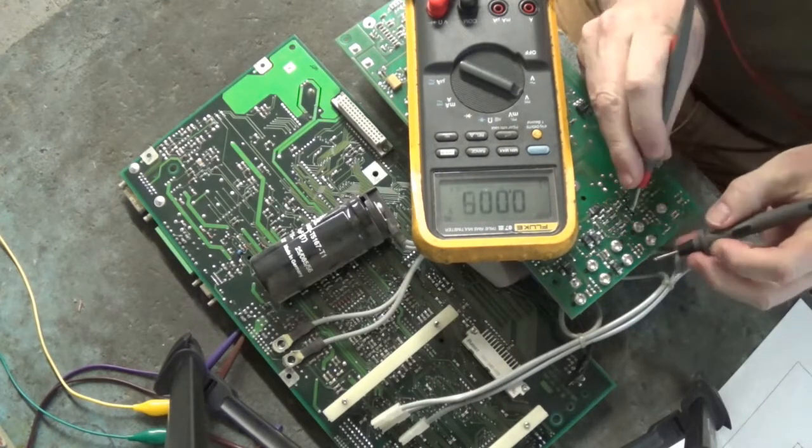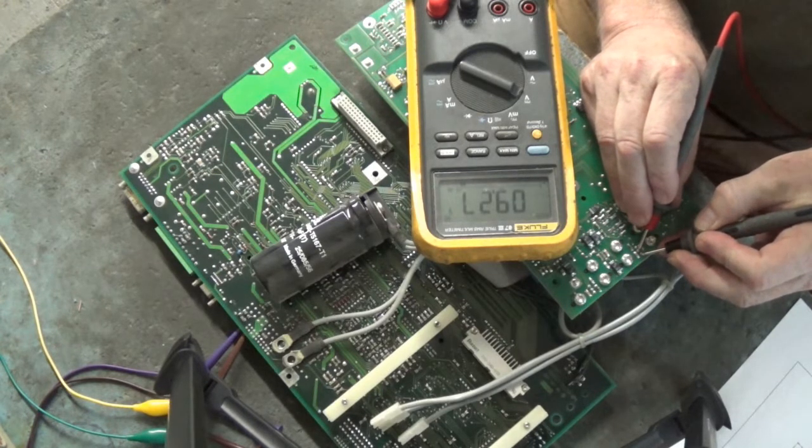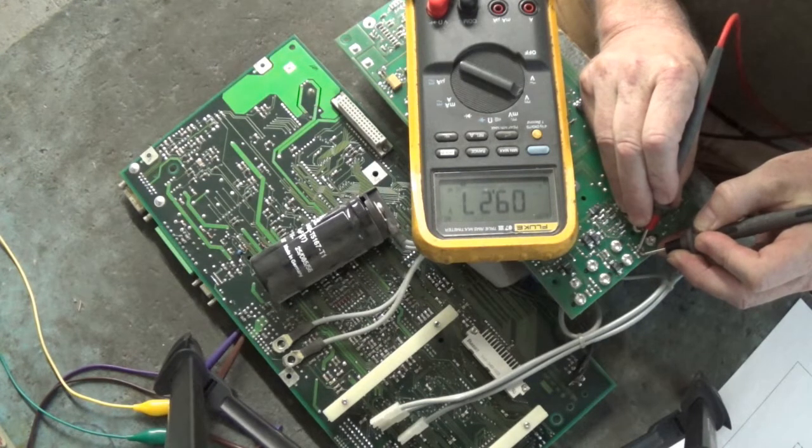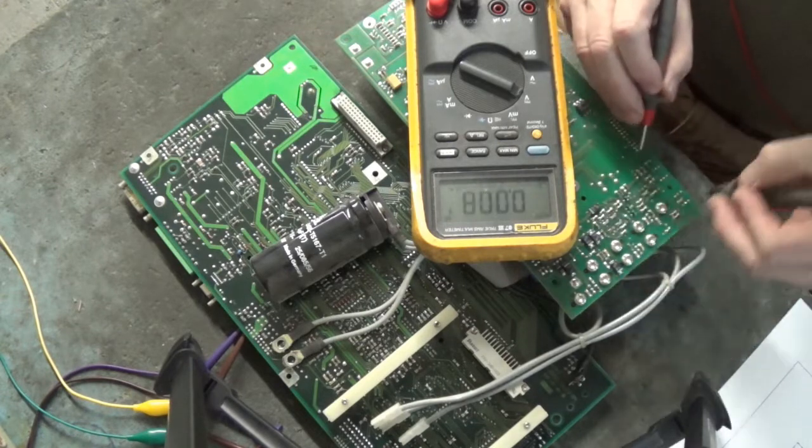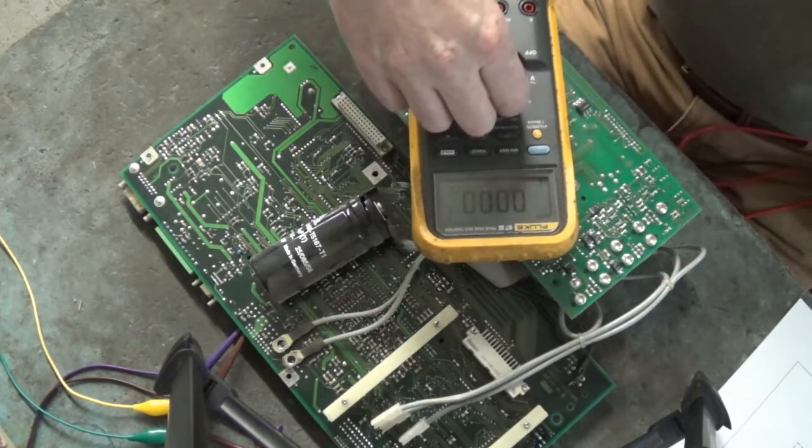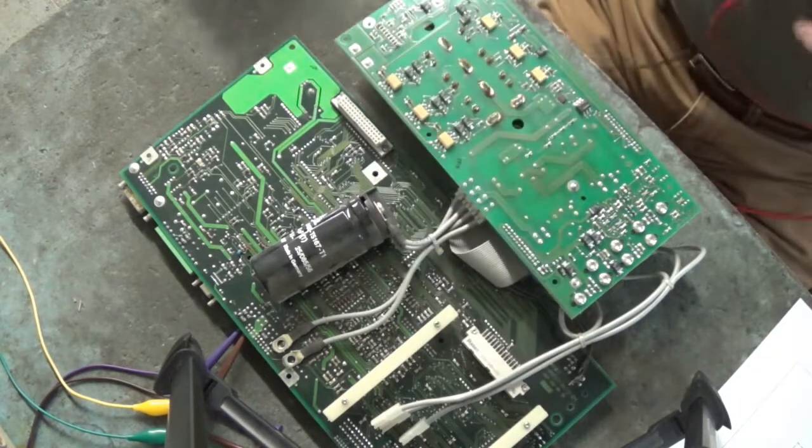This one here, something's going on with this one here. Its output is higher than the others at 9.27 volts DC. We'll pull these current senses and put some new ones in there.